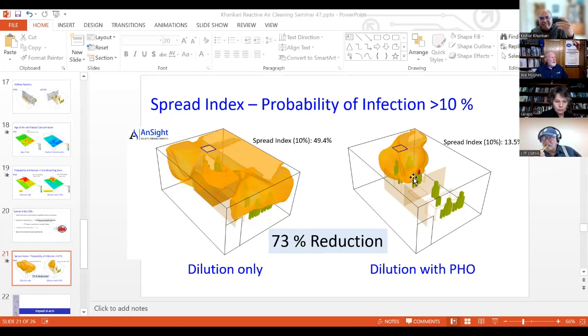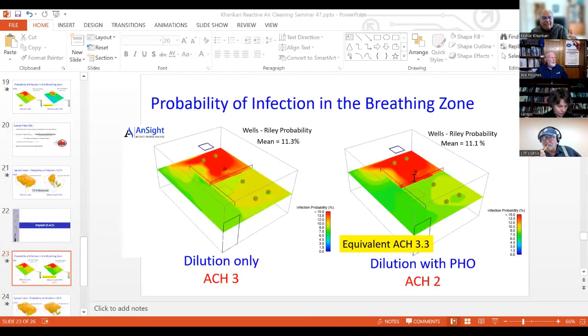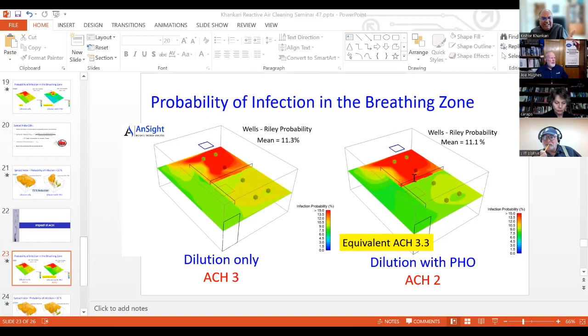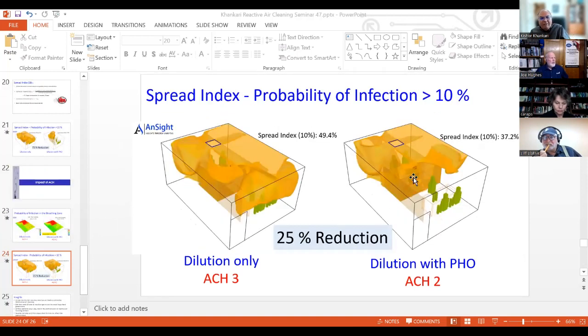Then we tried one more thing: instead of 3 air changes, what if we do 2 air changes, reducing the airflow? The results are pretty equivalent to dilution. So if you're using these reactive technologies, you can reduce your supply airflow, your air changes, by almost 33%. And again, the similar cloud shows that even with 2 air changes, we can relieve these three guys from that dirty zone.